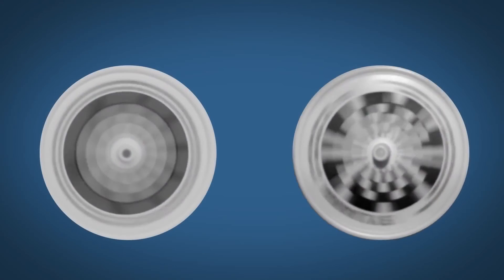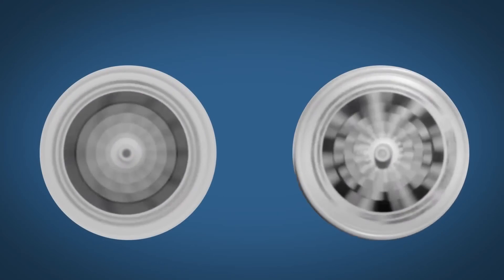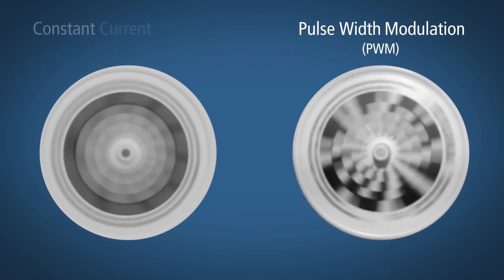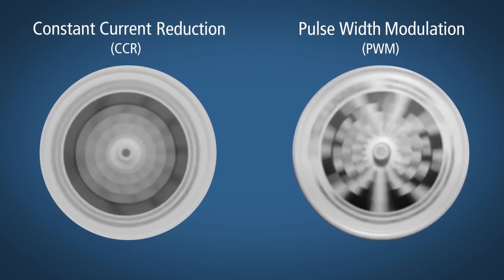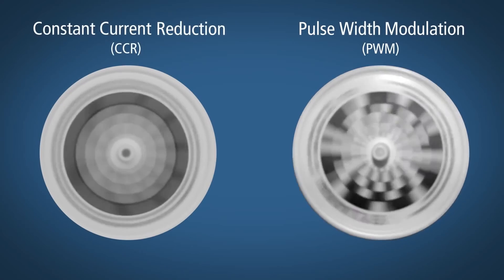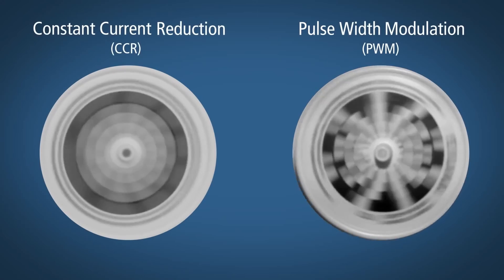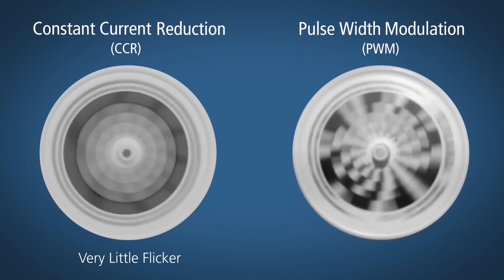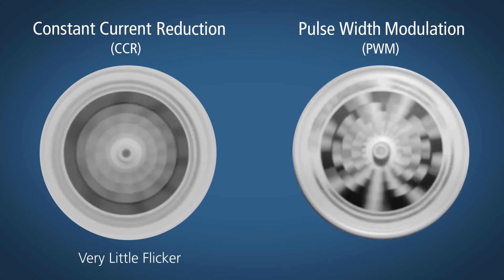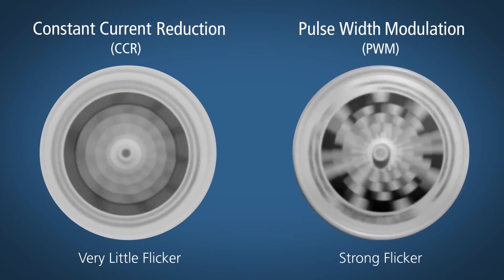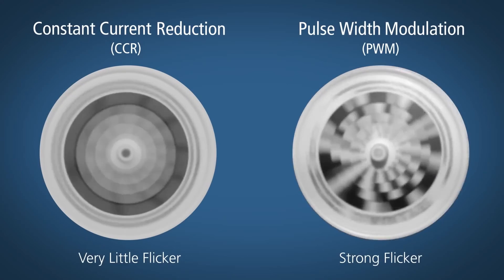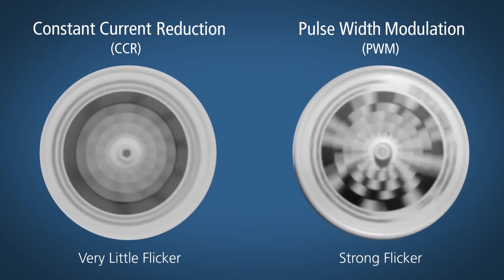Let's take a look at the patterns that emerge from an LED light source driven by a dimmed PWM LED supply and a dimmed CCR LED power supply. The wheel on the left, driven by a CCR power supply, tends to show constant concentric circles — a sign of a luminaire that has little flicker. The spinning wheel on the right has clearly chopped-up segments: you're seeing the strobe effect, which is perceived as flicker.